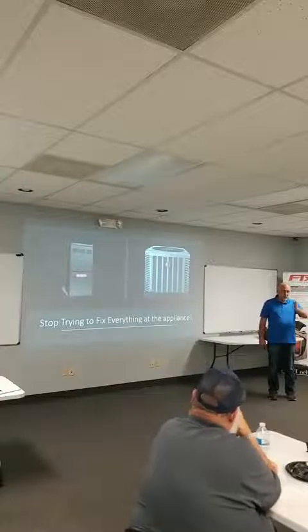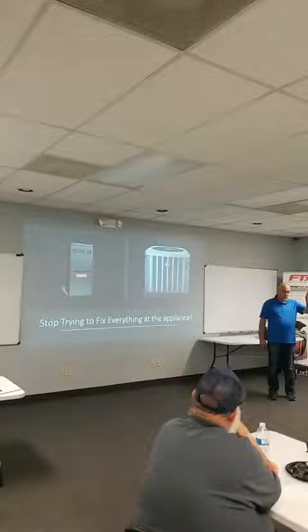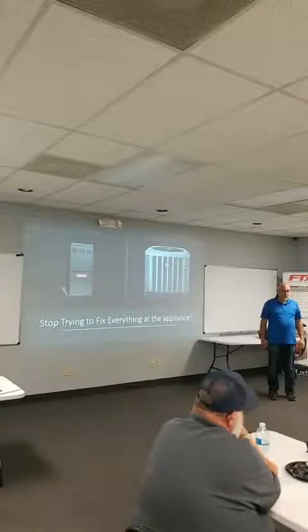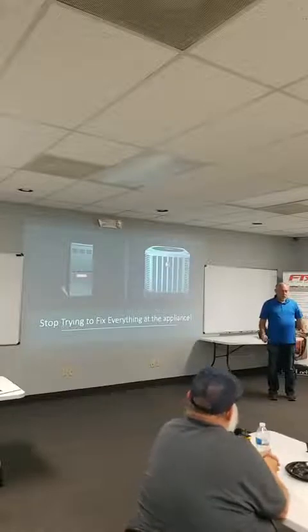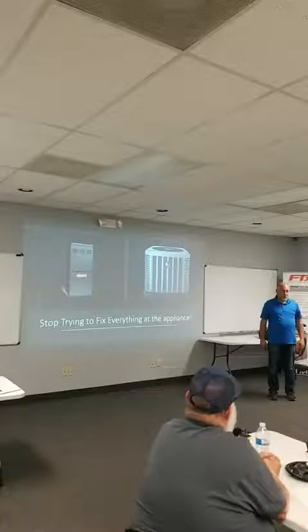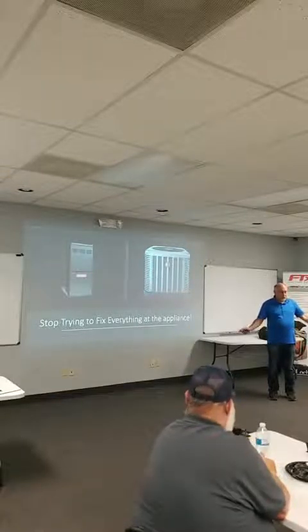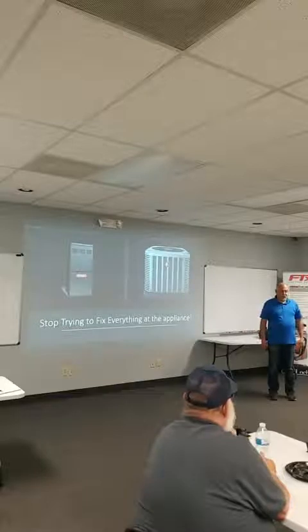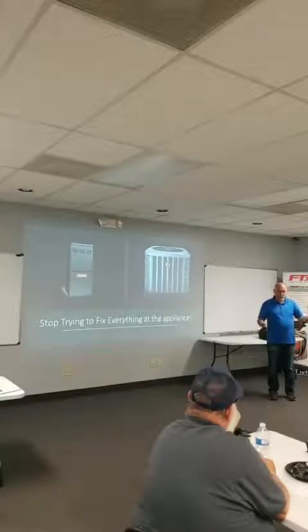Chiller 1 shuts off. Chiller 2 shuts off. Chiller 3 shuts off. Chiller 4 goes to run on the unloaders on an 80 degree day, right? They saved so much money, that drive paid for itself probably in the first month and a half out there, right? But everybody at Gardner went out there and they would service the chillers, and they would put their gauges on, and they'd look at things, they measure superheat, they measure subcooling. And the chillers were running fine because they were running balls to walls. Nobody looked at the system, right?